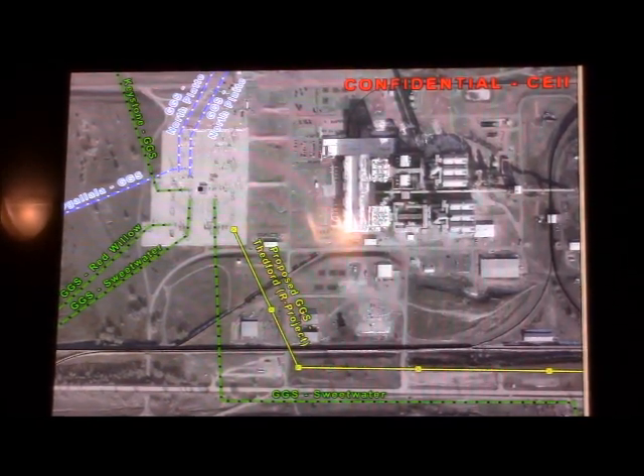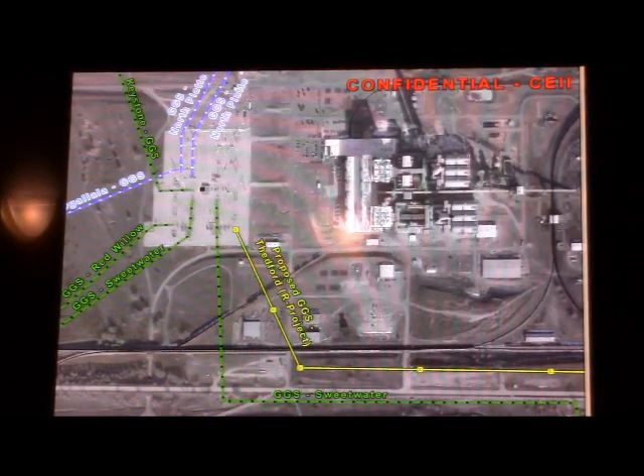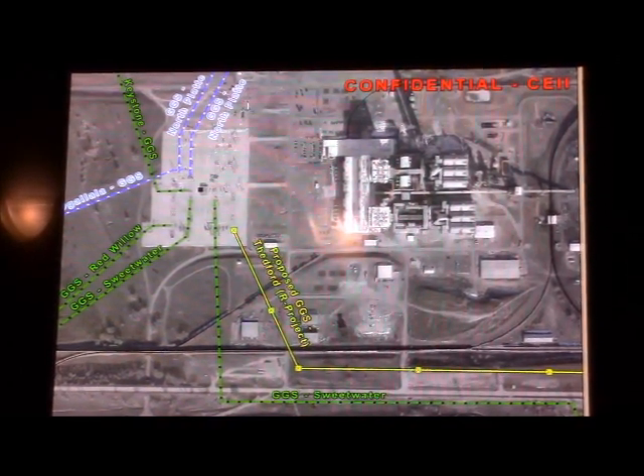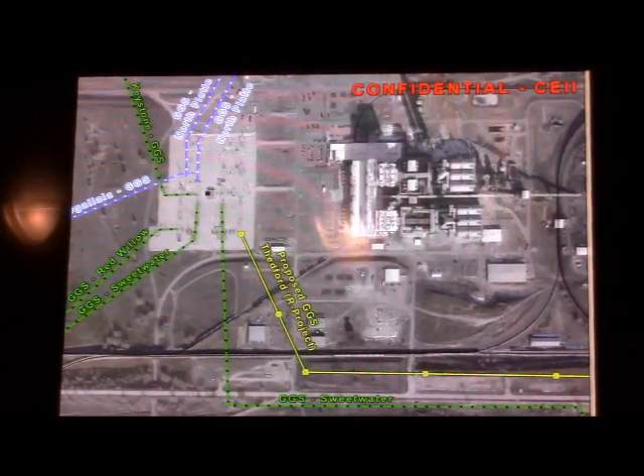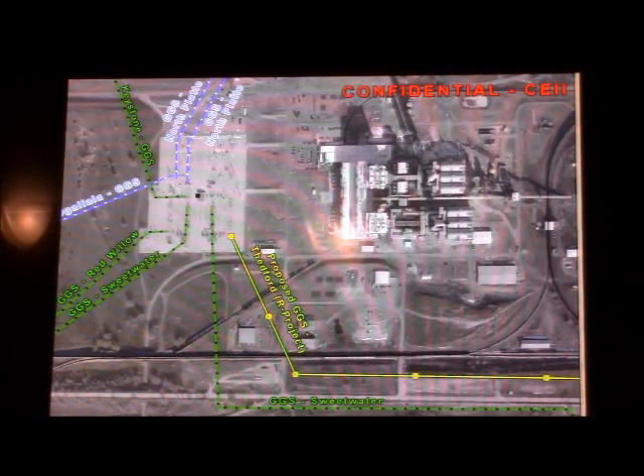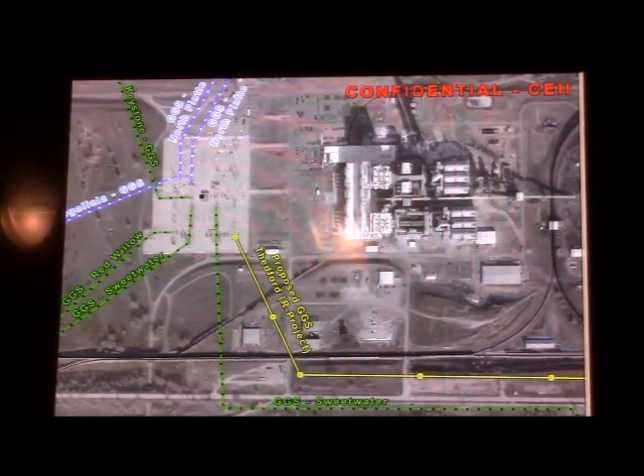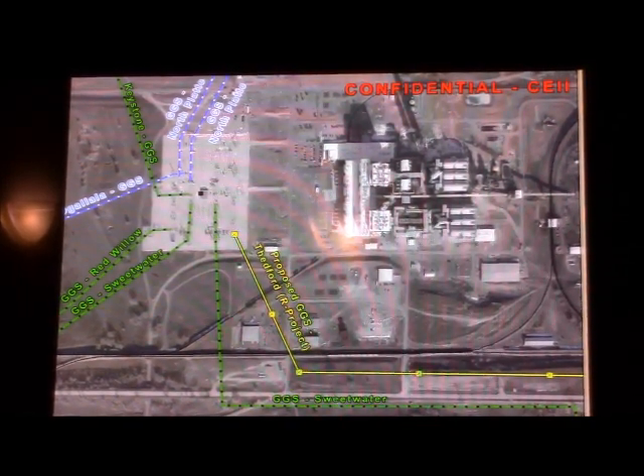All these green lines are existing 345 kV lines that terminate in that switchyard, and all the blue lines are existing 230 kV lines that terminate in that switchyard. So to avoid a high number of line crossings or switching the entire substation around in order to rotate so you could actually go out of a different bay, this really is the best way to get out.